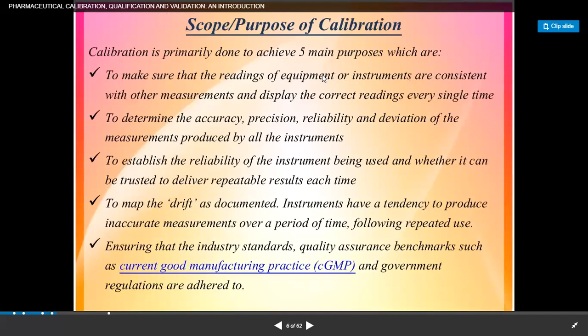Now, the scope and purpose of calibration. What is the scope of calibration? Calibration has basically five main purposes: to make sure that the readings of equipment or instruments are consistent with other measurements and display the correct reading every single time; to determine the accuracy, precision, reliability, and deviation of the measurements produced by all the instruments; to establish the reliability of the instrument being used and whether it can be trusted to deliver repeatable results each time; to map the drift or changes.